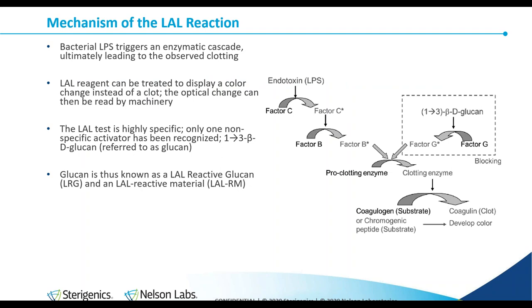It's important to note that endotoxin is not directly measured — what's actually measured is the clotting or the development of color. When you get results for an endotoxin test, you're told how reactive the test was, not how much toxin there is. This reactivity is reported in endotoxin units (EU) in the USP; some compendia use international units (IU), and 1 EU equals 1 IU. One EU is equivalent to approximately 0.1 nanograms of E. coli endotoxin, which is 0.1 parts per billion. The most sensitive tests available, down to 0.001 EU/mL, can detect 0.1 picograms per milliliter — one part per trillion.